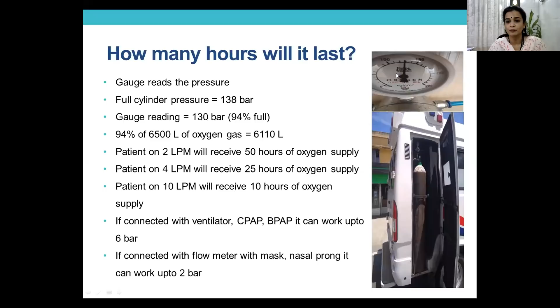Now, typically this D-type cylinder, when you are connecting to a machine, to a ventilator, CPAP, BiPAP, it can work up to 6 bar, which means the pressure up to which the machine can take. So if it is not connected to a machine and it is directly through a mask or a nasal prong using a flow meter you're connecting, it can go up to 2 bar, which means till the end. So this is how we calculate how long it works.